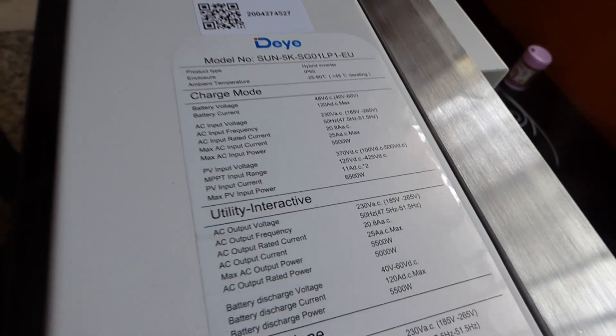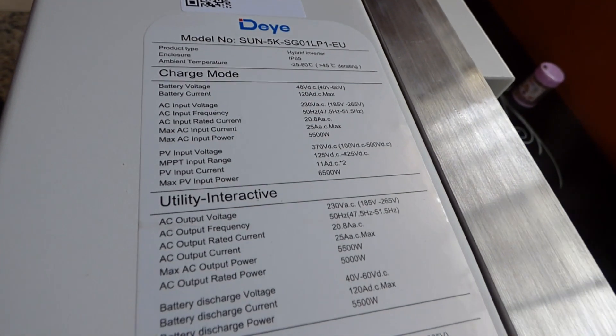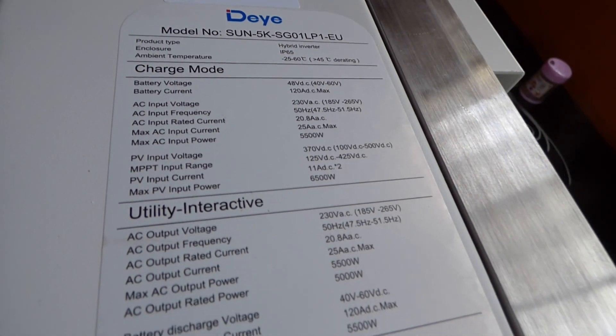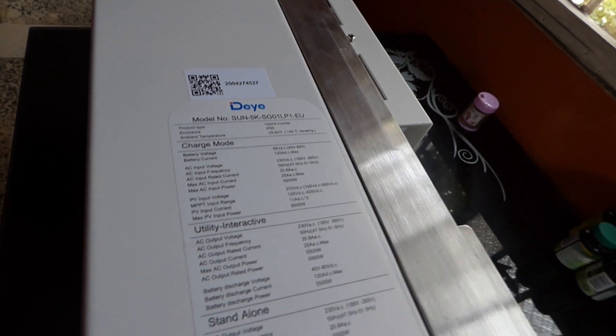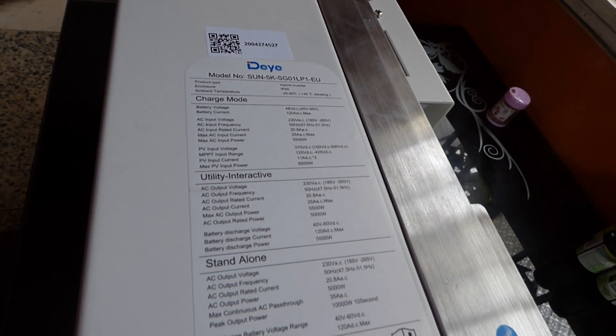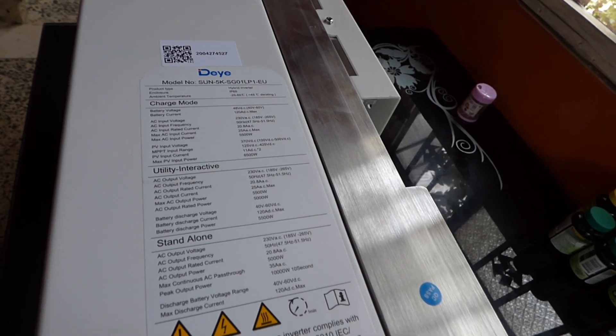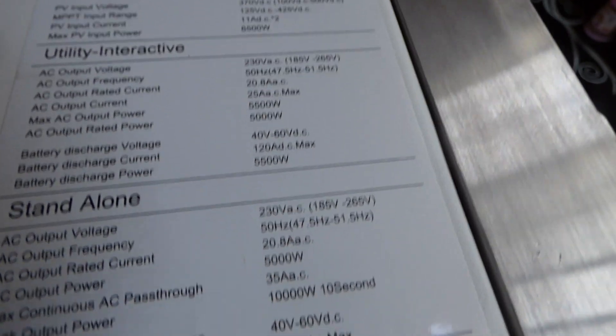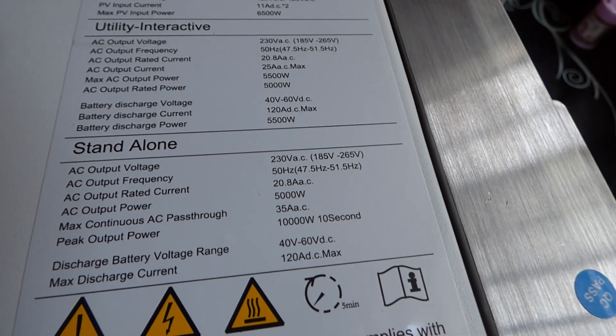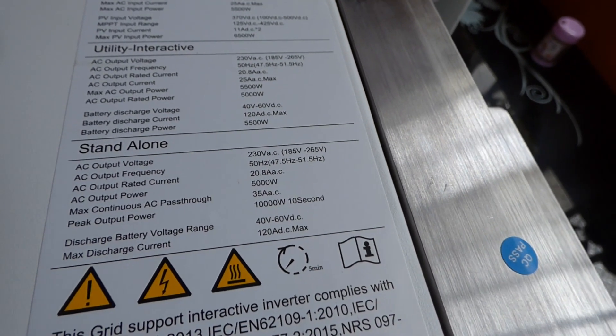Here is the label on the side. The model is SUN-5K-SG01LP1-EU. They also make for Sol-Ark and SunSynk, so it's the manufacturer for multiple people. Battery voltage is 48 volts, ranging from 40 to 60 volts. Battery current is 120 amps — so this can output 120 amps. That number is mind-blowing for a high-frequency inverter. Its surge rating is 10 kilowatts, and AC output stand-alone is 5,000 watts — the surge is 10 kilowatts for 10 seconds.